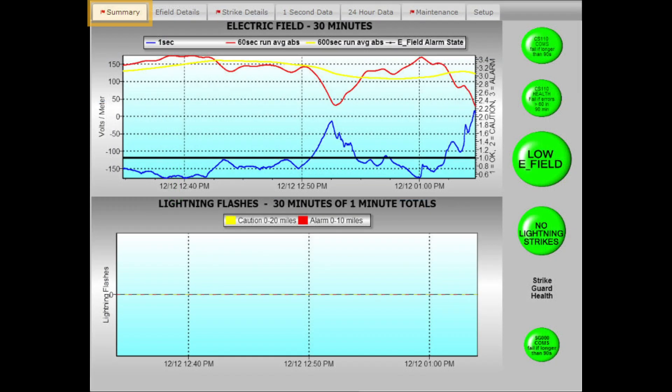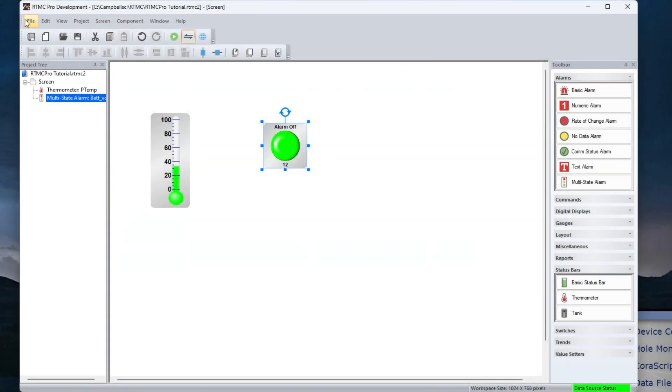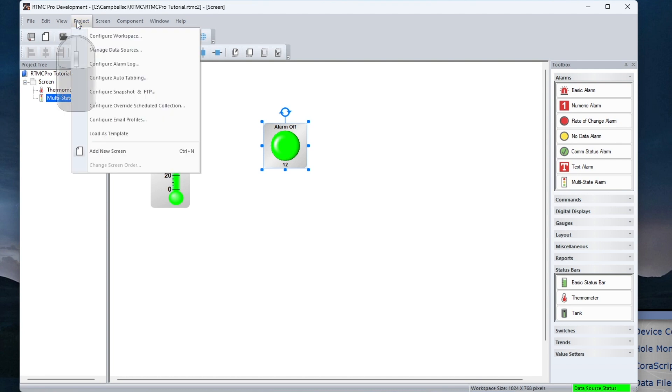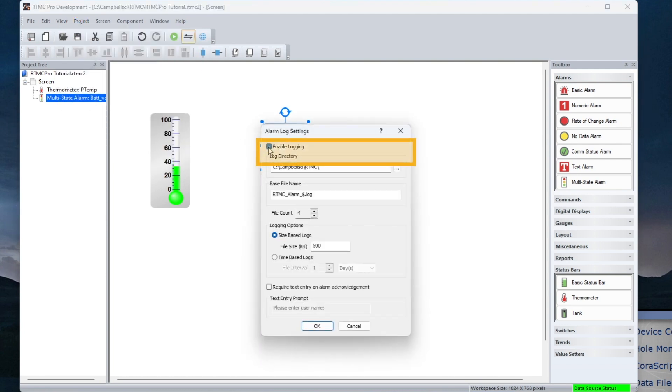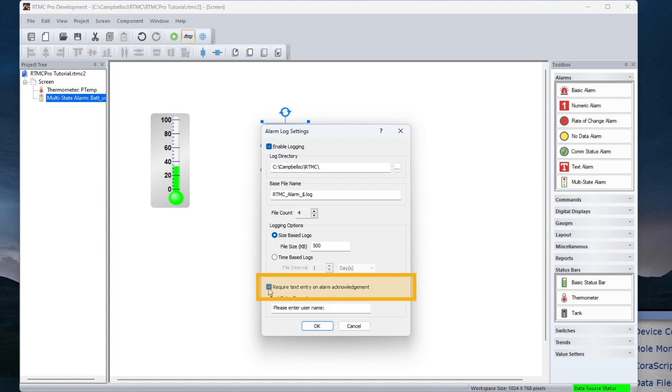I'll also see in this multi-tab project that a red flag appears on the tabs with active alarms. I can also keep a log of all project alarms. Enable Logging here. When this box is checked, a text entry is required of the person acknowledging the alarm. This makes it possible to log information about who acknowledged the alarm along with other comments and observations.